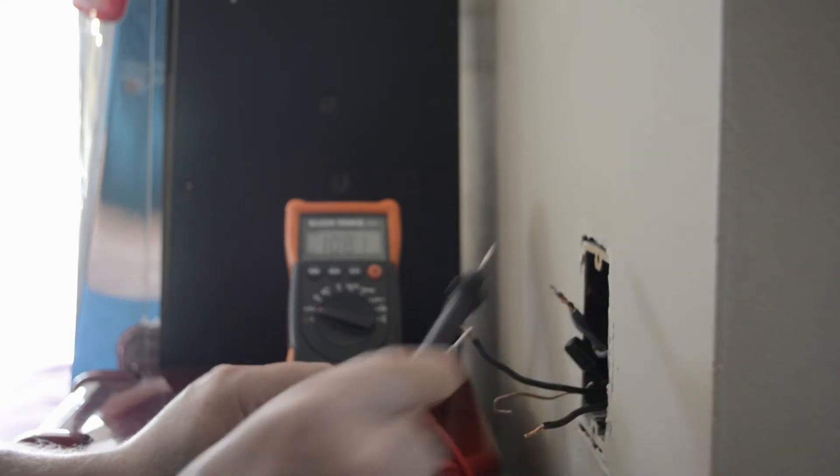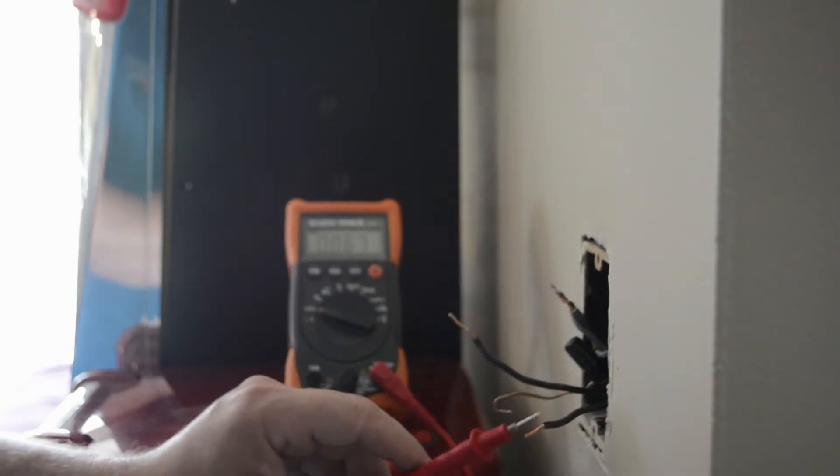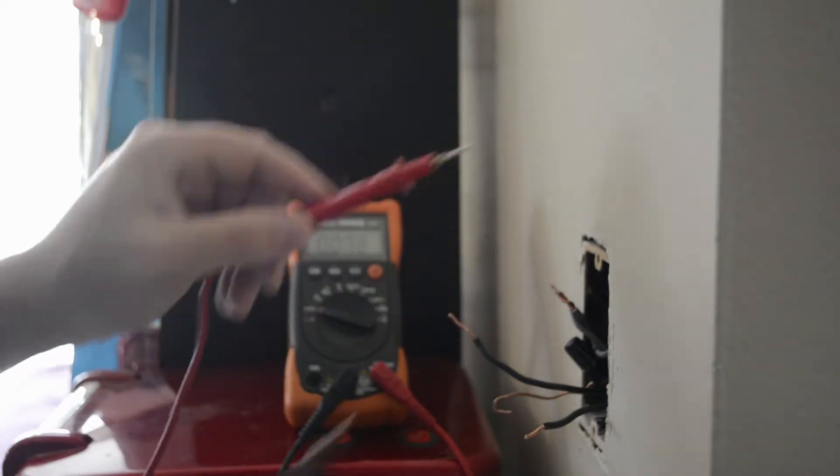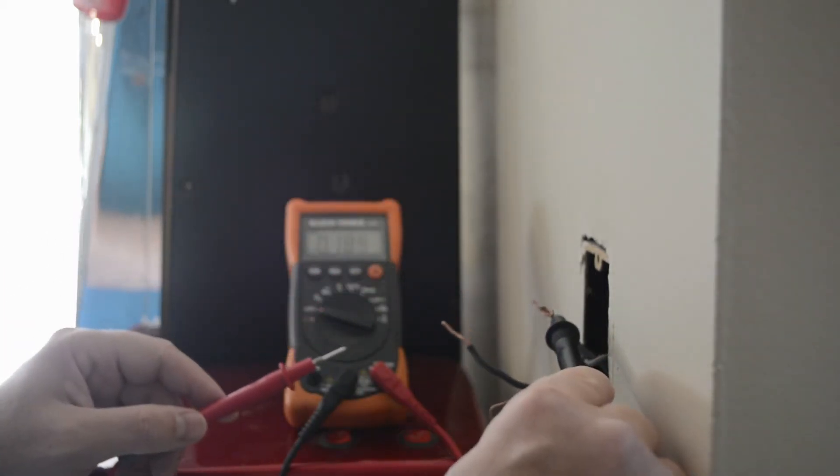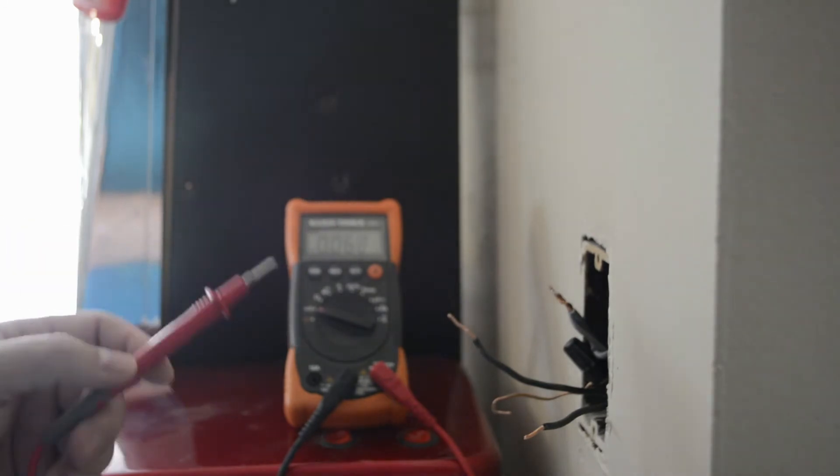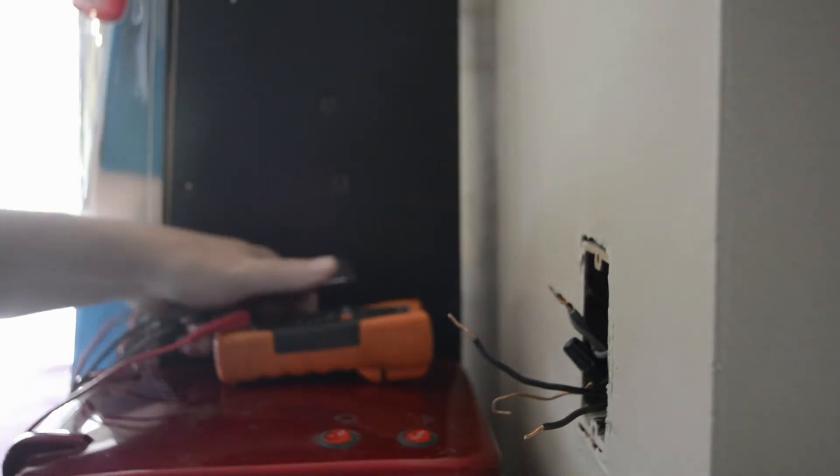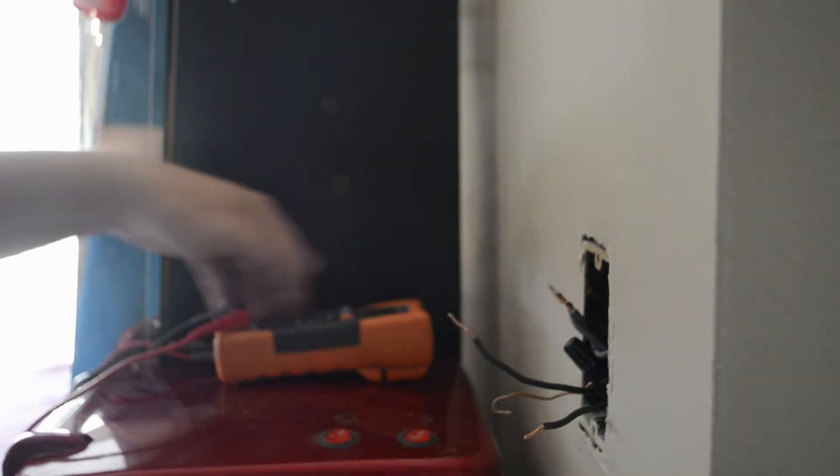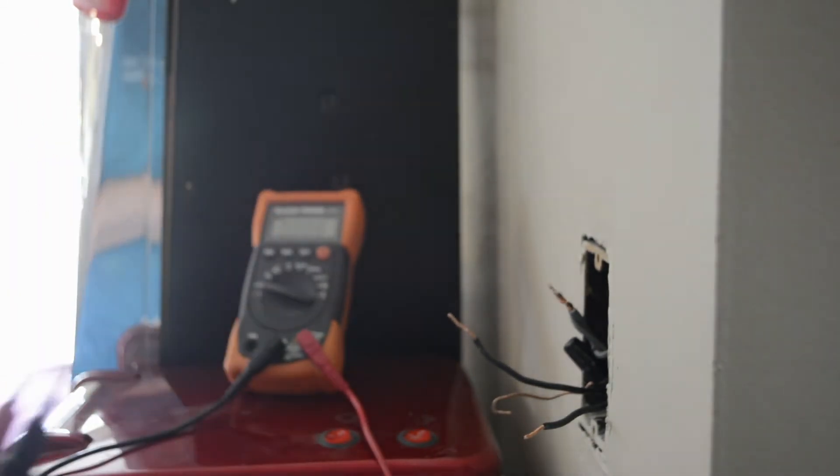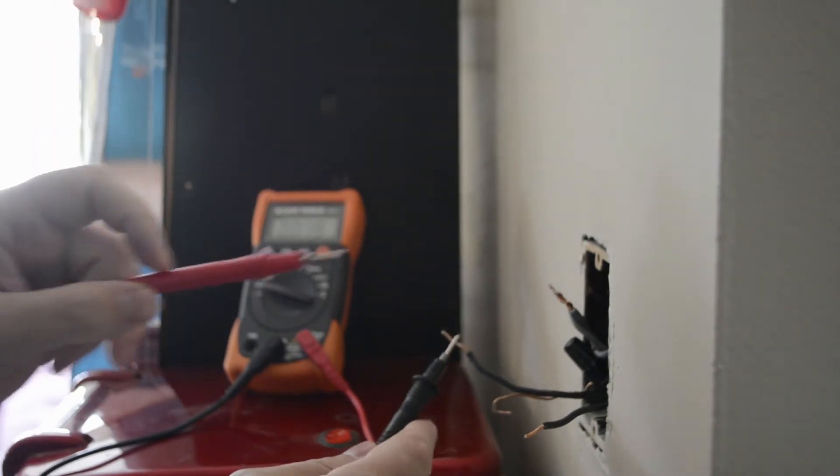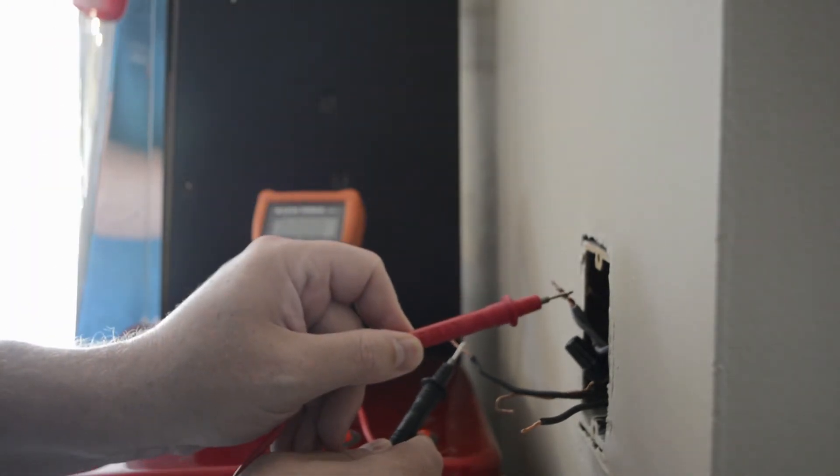This is my line and this is my load. And then my neutral is the white, or in my case, gray wires. I'm going to turn the power back off for the actual wiring. Power is turned off. And I can verify that by touching this lead and this one. And there's no voltage. Power is off. It's safe to proceed.